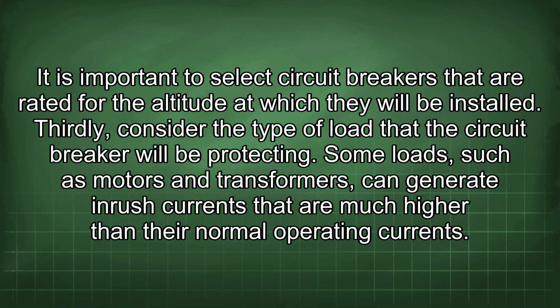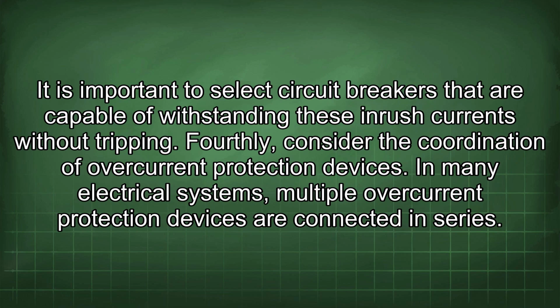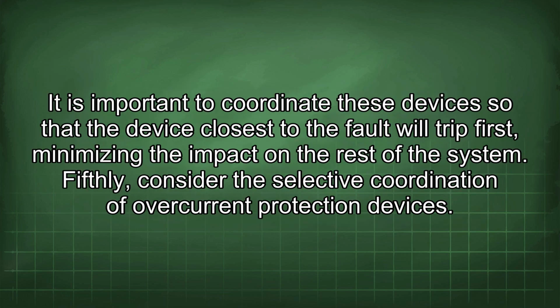Thirdly, consider the type of load that the circuit breaker will be protecting. Some loads, such as motors and transformers, can generate inrush currents that are much higher than their normal operating currents. It is important to select circuit breakers that are capable of withstanding these inrush currents without tripping. Fourthly, consider the coordination of overcurrent protection devices. In many electrical systems, multiple overcurrent protection devices are connected in series. It is important to coordinate these devices so that the device closest to the fault will trip first, minimizing the impact on the rest of the system.